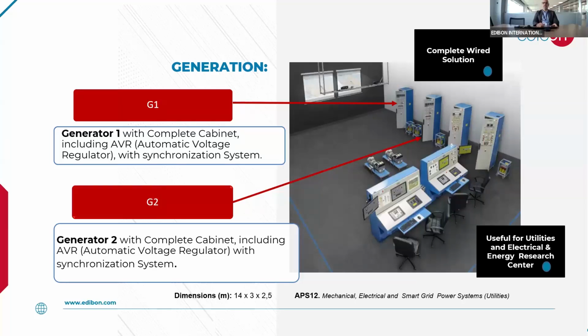We all know that in order to connect generator 2 with generator 1, or any parallel generators together, you have to be sure that they are in the same three factors: same voltage, same frequency, same sequence. So this equipment already includes the synchronization panel.